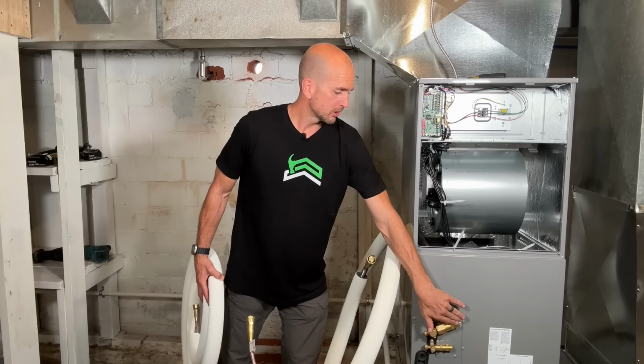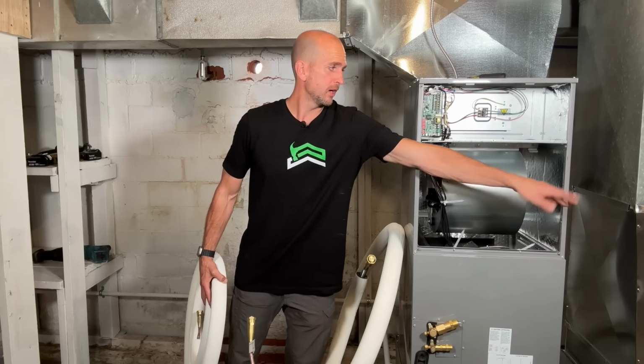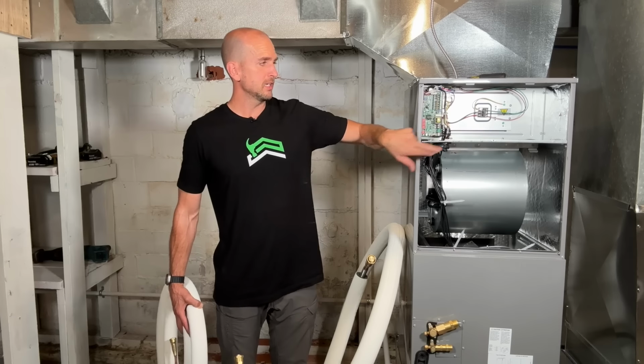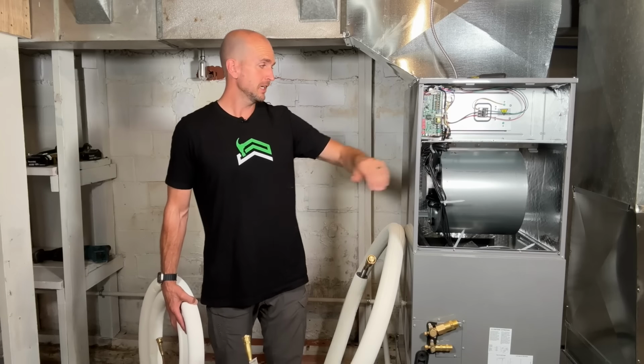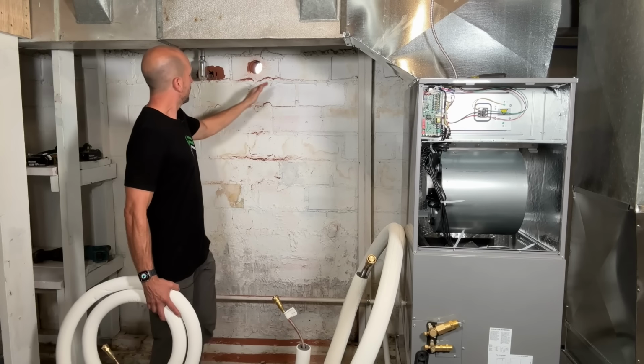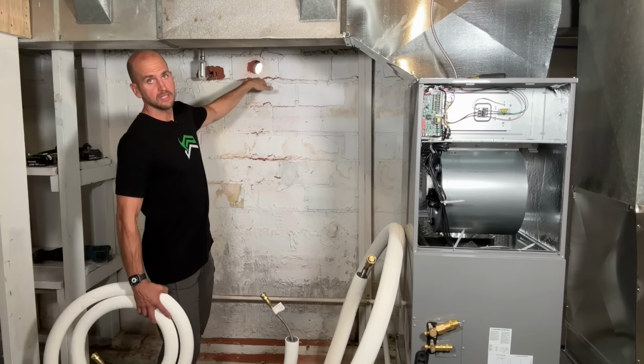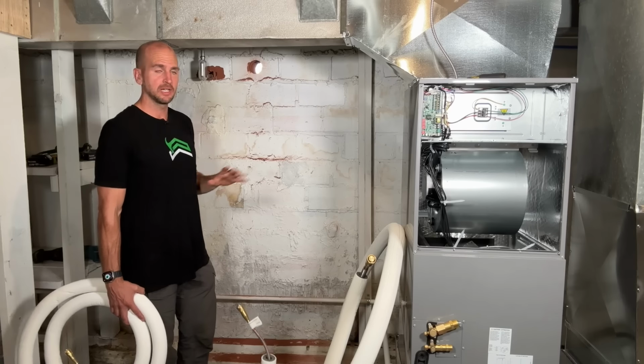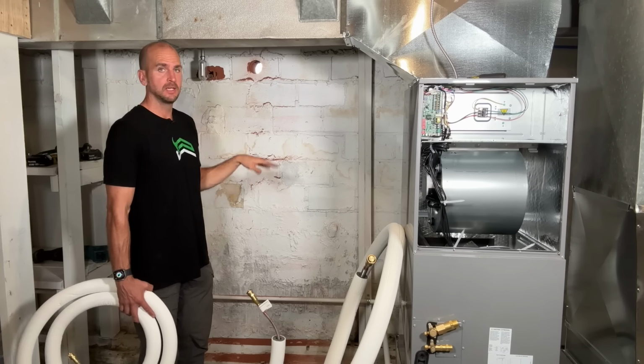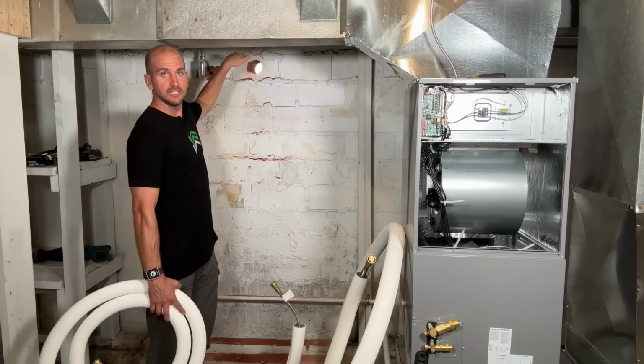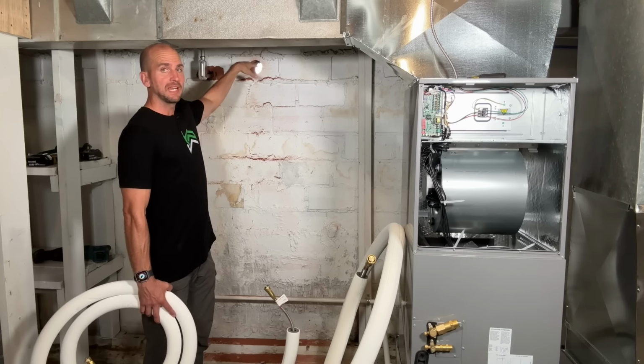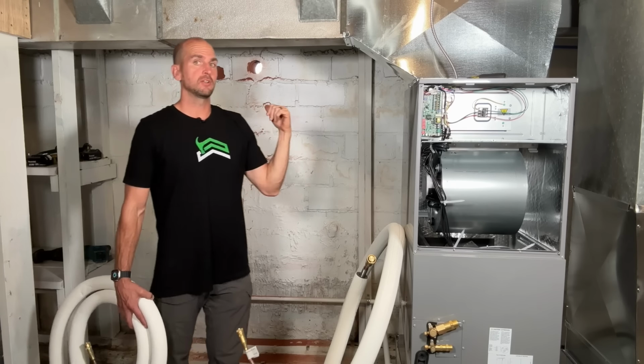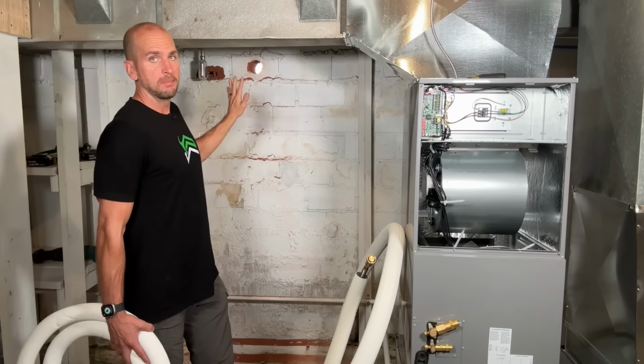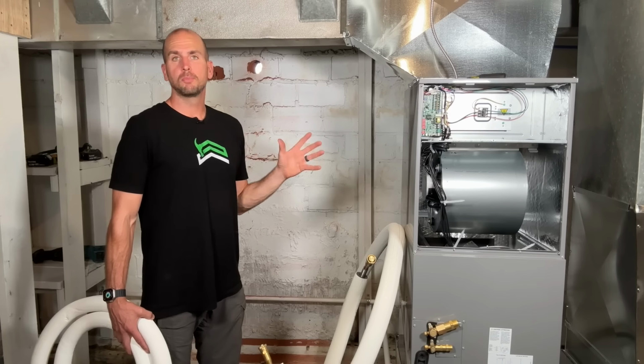I plan on coming through here, wrapping around between the air handler and the cold air intake, and then coming out on my back wall and going straight out right into the unit. Any extra line I plan on leaving inside the basement, and then having a fairly clean install right to the outside unit, which is only a couple feet from that hole or from my basement wall. So you'll have a little back and forth.